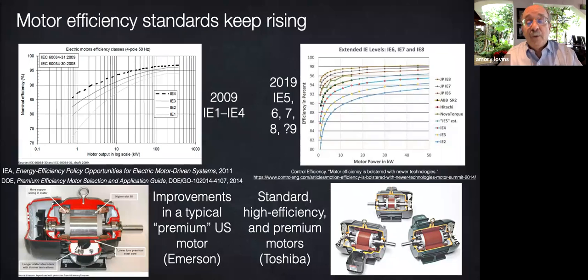And in 2017, an IE8 rare earth-free synchronous reluctance motor from SRAMtechnology.com was advertised, 95.86% efficient at 2.2 kilowatts. At the other end of scale, a giant ABB synchronous motor, 44 megawatts, achieved 99.05% efficiency. Now, looking at these charts, you might think, well, so what? Gaining just 4 percentage points, say going from 92 to 96%, isn't so important.